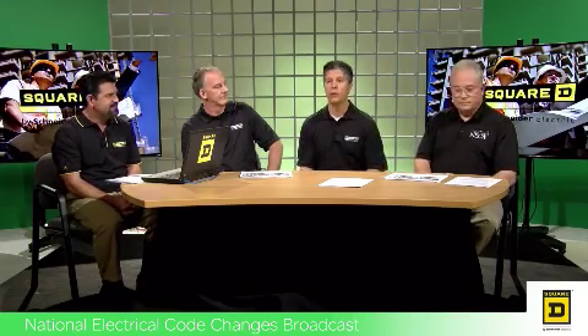Thanks, Phil. We start right out of the gate with one of the most important and significant changes in the 2017 National Electrical Code. Non-dwelling or non-residential service installations at 1,200 amperes or more will have a new arc flash hazard marking.